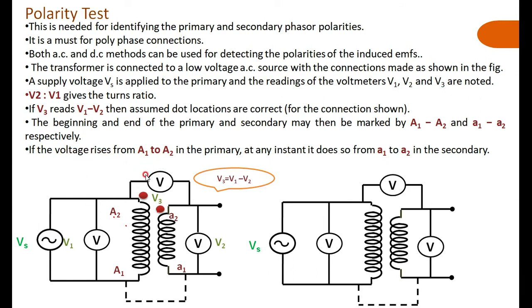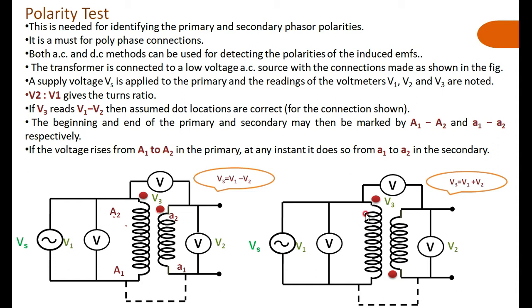If the voltmeter reads the sum V1 plus V2, then the polarity connections are not correct. Observe the second figure: the voltage V is applied and voltages V1, V2, and V3 are measured. In this case the voltmeter reads V1 plus V2. This means the polarity is such that there is a rise in potential from one point to another in both the primary and secondary, causing V3 to read V1 plus V2.